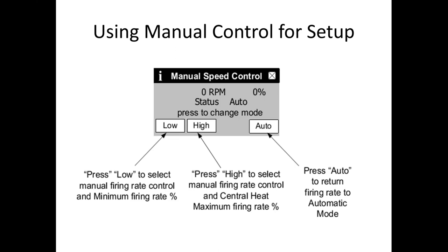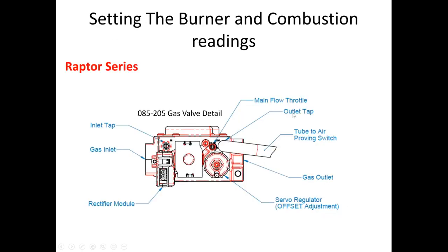Especially when we're doing our LP conversion kit, doing our LP testing, we're double checking our combustion as we change it for altitude. We need to throw a lot of heat out. Low fire is then tested after we get the high fire dialed in. That's what we're talking about right now, getting these things dialed in.